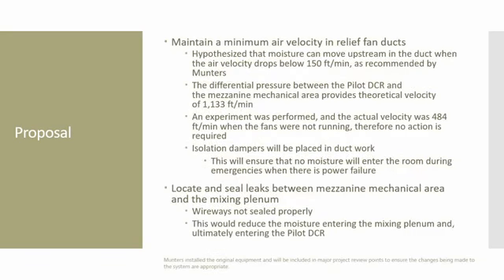With the old trigger condition, our project sponsor was concerned with moisture moving into the dry clean room through the exhaust vents. We determined that even if the exhaust fans were not on, the differential pressure in the room would provide a fast enough velocity through the vents that moisture could not travel upstream. This was then validated through an experiment of testing the airspeed in the vents. Isolation dampers will be installed into the vents to ensure we keep moisture out of the rooms in case of a power outage.